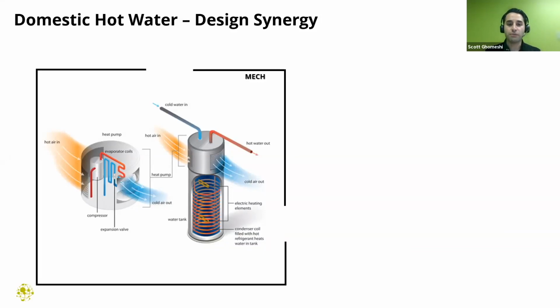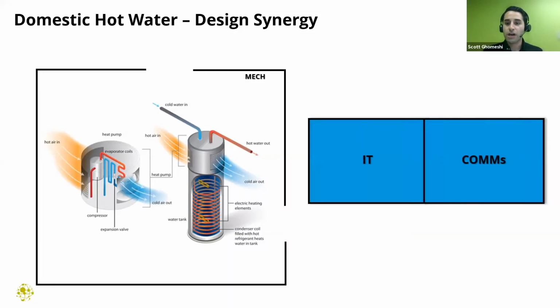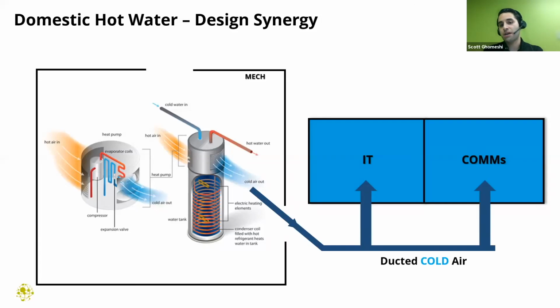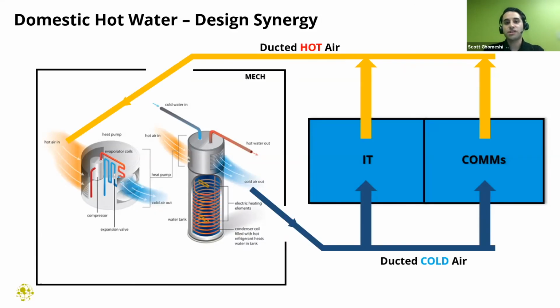Now, if this thing is just spewing out a whole bunch of cold air, finding opportunities to utilize that is key. For us, particularly in a firehall with IT and comms rooms, through some of the work we did with HCMA early in the project, co-locating these rooms—which have cooling-only process loads happening 24/7—allowed us to duct that cold air into these spaces, and let the hot air transfer back in, creating a passive cooling effect.